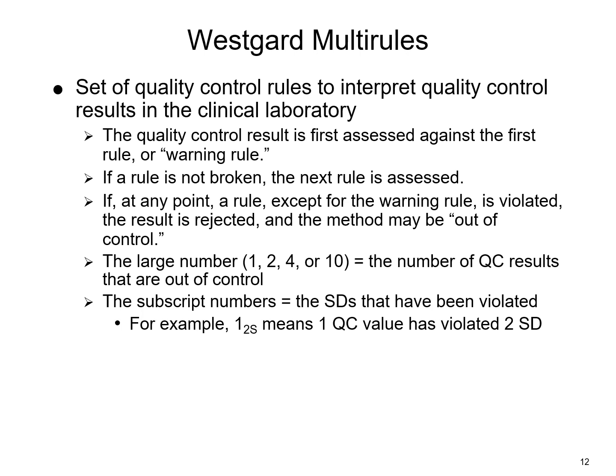And so we use the Westgard rules in order to determine, do we accept the QC run for the day? Do we just consider it a warning for the day? Or do we need to investigate some problems and not send out our patient results? So we use these rules to assess when we start seeing things go wrong. So the first thing we've got to do is look at the rules. We've got to follow them step by step to determine if any of those rules are broken.